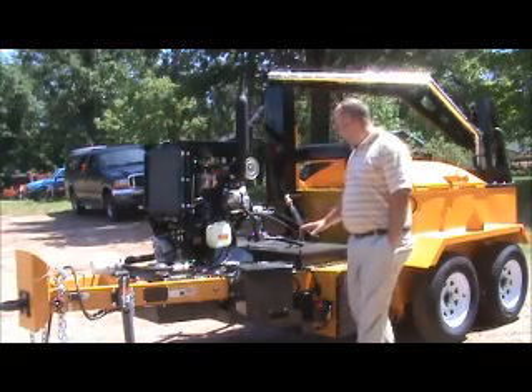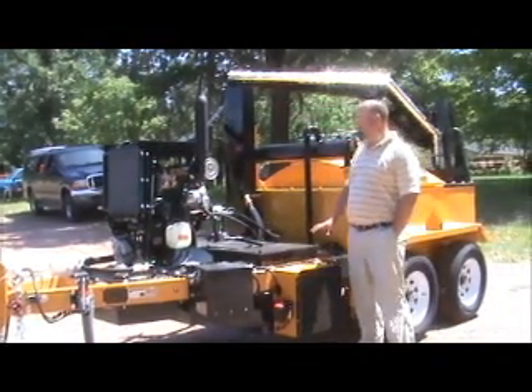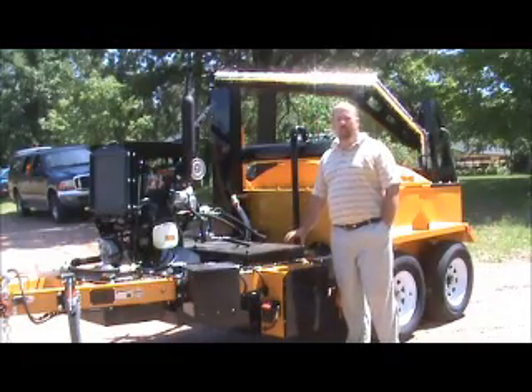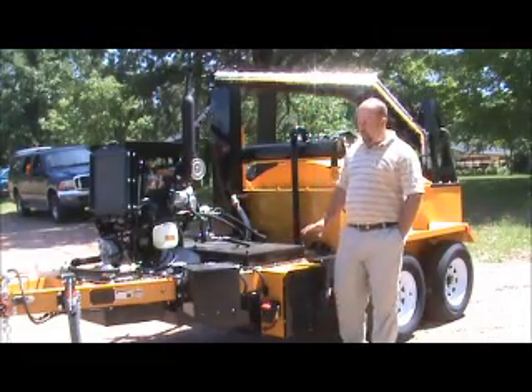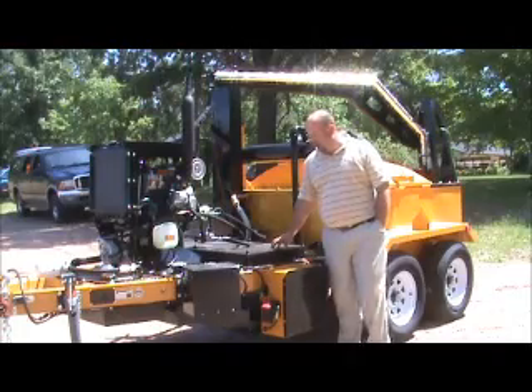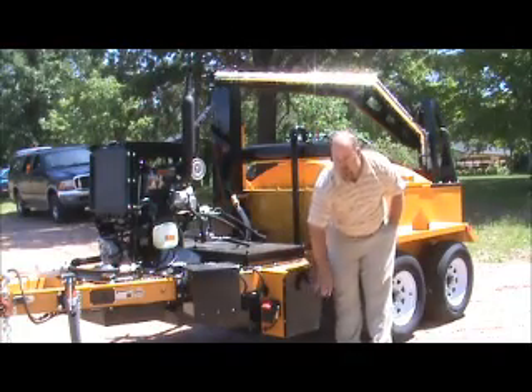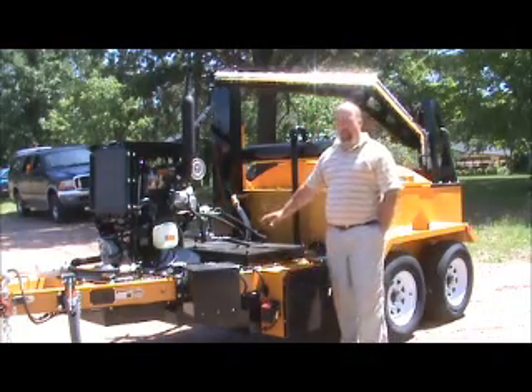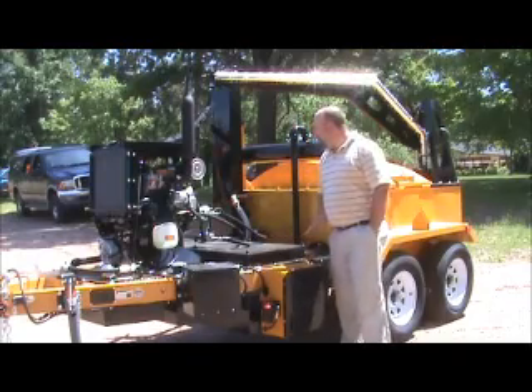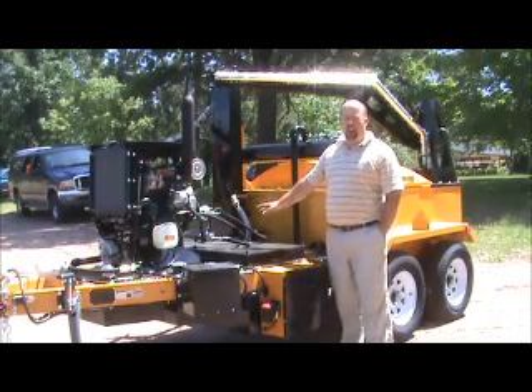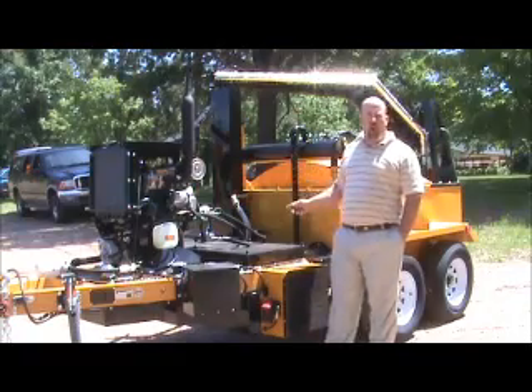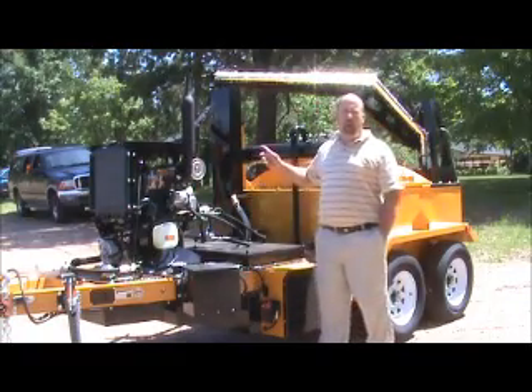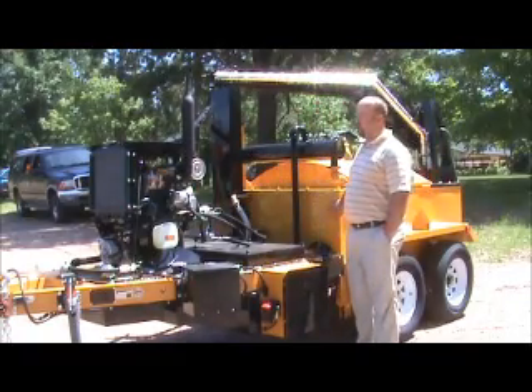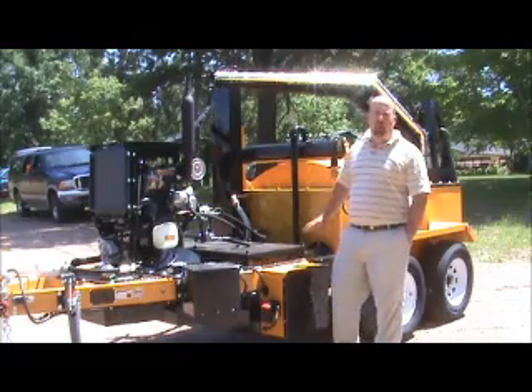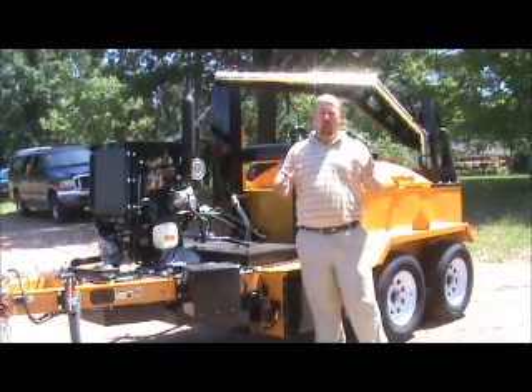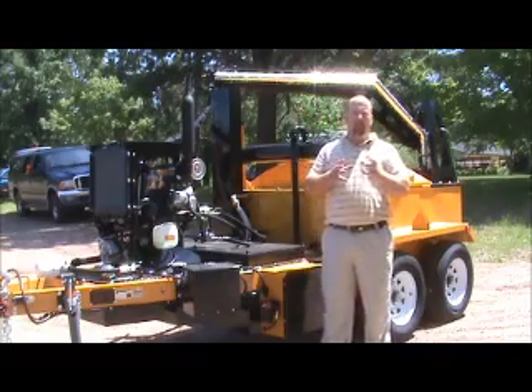The next thing we're going to talk about is our burner system. This is a very unique system on this kettle. We actually have what we call a heat exchanger on this unit. Our burner actually sits below this cover, and it fires into this big black box here, and the burner fires down through the inside. Now on the inside of that, there's a coil. Inside of that coil is our heat transfer oil. Because this is built kind of like a double boiler, we're actually heating up an oil tank, and our oil is actually melting our product.